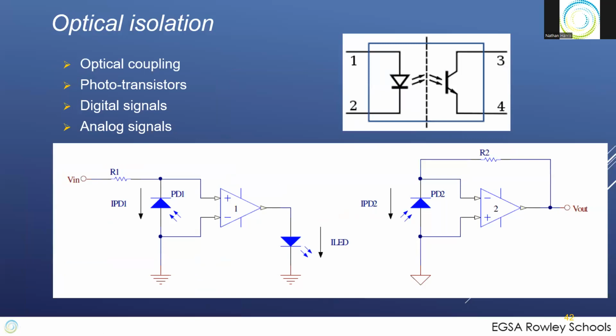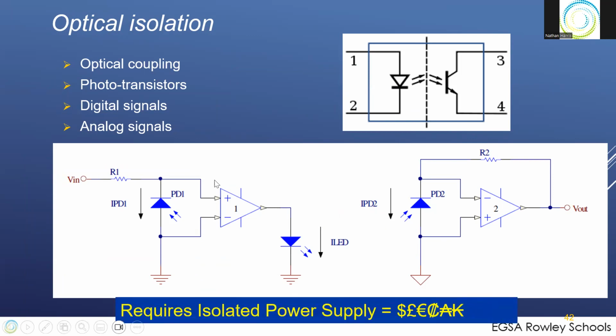Another type of galvanic isolation is optical isolation. And these are optical phototransistors. It's the analog signal. Sometimes it's chopped and then filtered at a high frequency. But at any rate, it's optically isolated from this light emitting LED to this receptor transistor here. It's good isolation. It tends to be a little more expensive though, because you have to have an isolated power supply for this circuit and a different power supply for this circuit, because the power supplies would then tie it together, wouldn't they? So you have to have an isolated power supply, which costs money. So we have to get this optical isolation involved in here, and this is the third type of galvanic isolation, and why it's so important to our control system to electrically isolate one system from another.